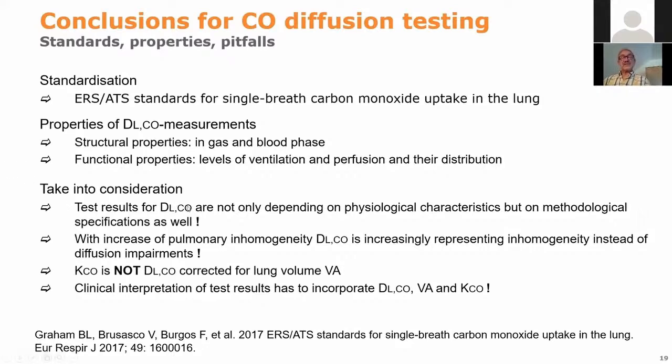The test results for DLCO are not only depending on the physiological characteristics, but on the methodological specifications as well. That means if you change the method, inspiratory time, expiratory time, breath hold time, that will change the test results. It's not only a physiological background.